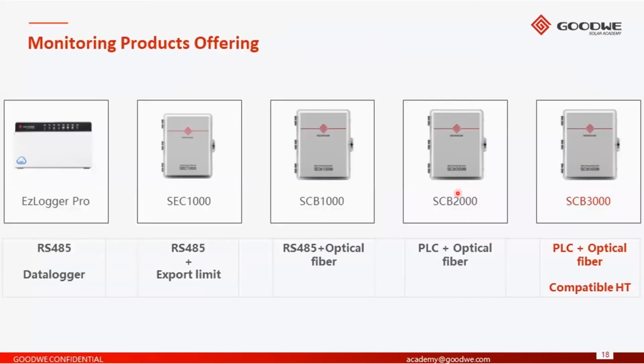So as I go through the monitoring solutions that are offered, we have the standard EzLogger Pro, which is very typically used for customers who just want to monitor their PV plant and they have less than 60 inverters on site. As we go here onto the SEC 1000, this is a nice C&I solution for customers that still wish to use the RS485, but also wish to have an export limit function. So inside the SEC 1000, we have the necessary components to realize an export control solution.